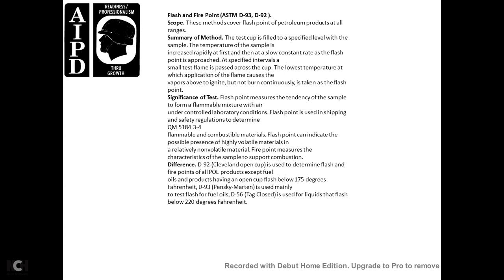Significance: flash point measures the tendency of a sample to form a flammable mixture under controlled laboratory conditions. It is used in shipping and safety regulations to determine if material is flammable or combustible. Flash point can indicate the possible presence of highly volatile materials in relatively non-volatile material. Fire point measures the characteristic ability of a sample to support combustion. D92 Cleveland Open Cup is used for petroleum oils and lubricants except fuel oil and products with open cup flash points below 175°F. D93 Pensky-Martens is mainly used for fuel oil. D56 is used for liquids that flash below 220°F.